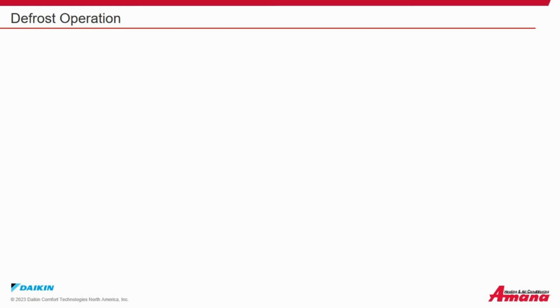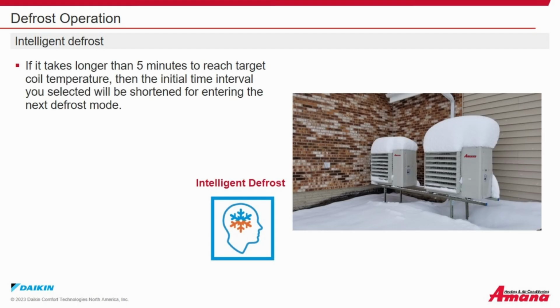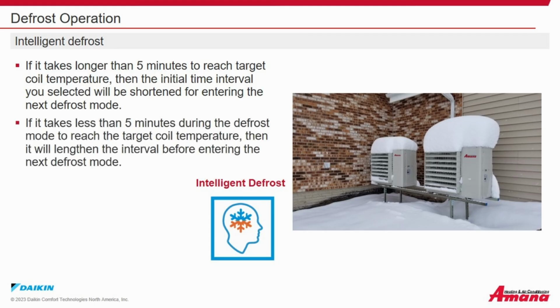Defrost operation. Intelligent defrost. If it takes longer than 5 minutes to reach the target coil temperature during a defrost cycle, then the initial time interval you selected will be shortened for entering the next defrost mode. If it takes less than 5 minutes during the defrost mode to reach the target coil temperature, then it will lengthen the interval before entering the next defrost mode.